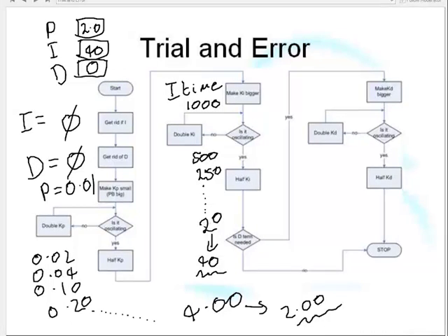So that's the trial and error method. The reason why we're not allowed to use the trial and error method in the field is because on 2 occasions now, we threw the valve into oscillation, and you're not allowed to oscillate real things. I mean, I can't emphasize this enough. You can imagine, if you went up and said, do you mind if I just oscillate the nuclear reactor level? No one's going to be very happy. So we're not allowed to oscillate real things. Most valves are pretty big. Oscillate them for a couple of minutes and you've stuffed the valve up.